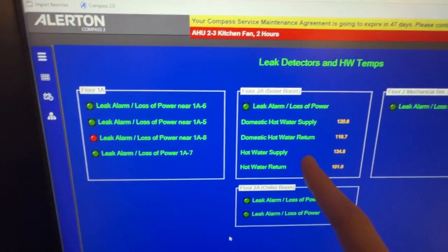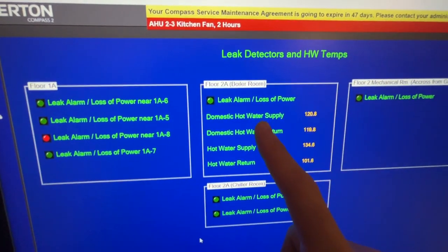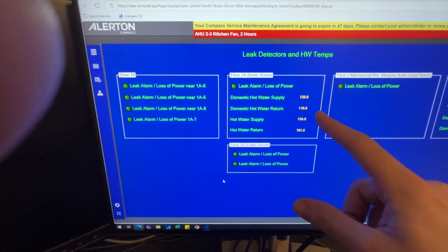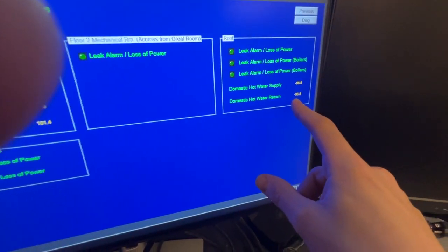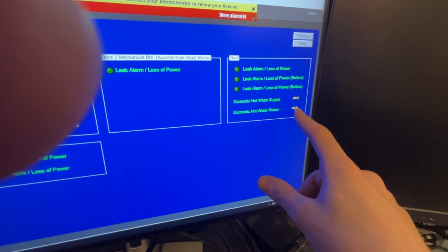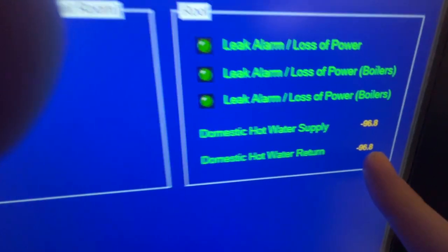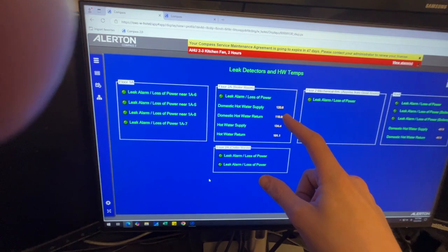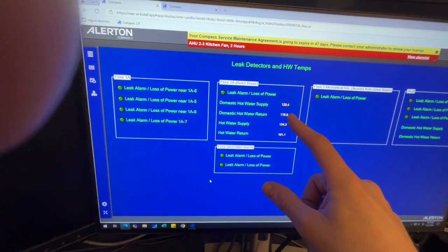And then we put the domestic hot water for the hotel here. I'm sorry, there's the 120 loop and the 140 loop. So kitchen, hotel, and then residences. Something is wrong with the residences one. I did not see this before, but something is not correct with that controller because it's reading negative 96. So they need to fix that. But this is good. We're right at 120.